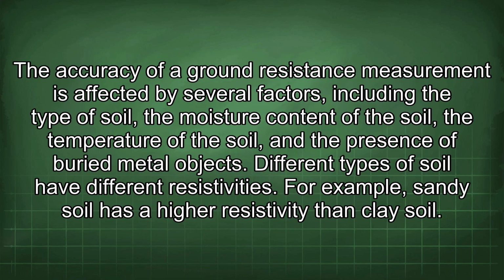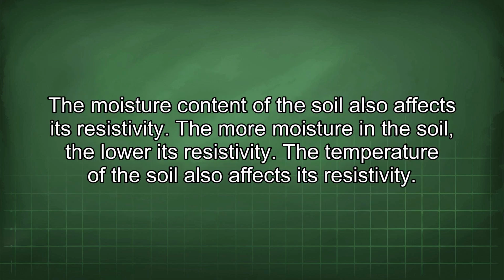The accuracy of a ground resistance measurement is affected by several factors, including the type of soil, the moisture content of the soil, the temperature of the soil, and the presence of buried metal objects. Different types of soil have different resistivities. For example, sandy soil has a higher resistivity than clay soil. The moisture content of the soil also affects its resistivity. The more moisture in the soil, the lower its resistivity.